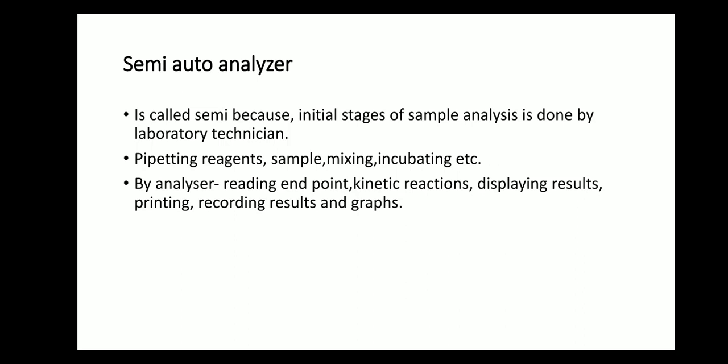So what all does the technician have to do? Pipetting the reagents. The technician himself has to take the pipette, pipette out the sample, pipette out the reagent, mix it, keep it in the incubator if any incubation is required, then carry it, put it in the analyzer, then take the reading. Giving the reading, displaying the results, printing the result, recording the results and plotting the graph, all this is done by the analyzer. The rest of the things are done by the technician. So it is a semi auto analyzer.